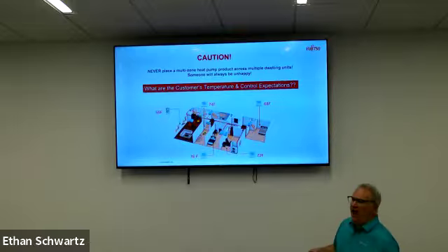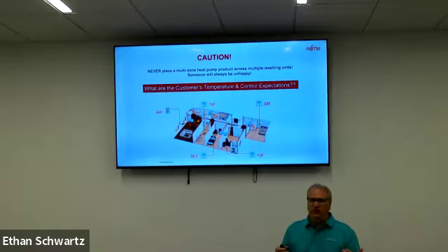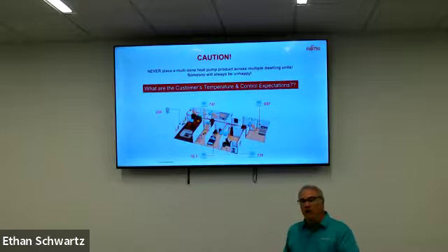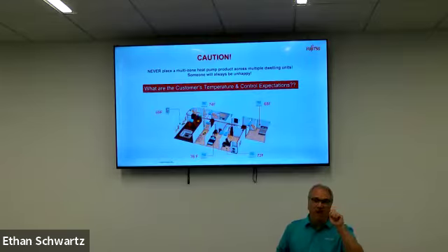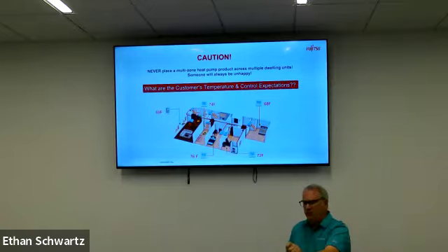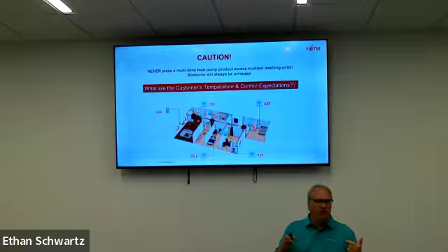If you're going to a mini split or an H series, there's no offering that Fujitsu currently has to be able to put those all in one central controller. We could do that through the VRF side on our controls, which I'll talk about in just a little bit. But overall, as an H series product, there's no control that would do that. However, on the VRF side, we have centralized controllers that will sit across refrigeration circuits and allow that occupant or manager to go to that controller and say, I want that room at this temperature, this one at another temperature. And if it's hooked up to heat recovery, you can determine if those are going to be in heating or cooling. So that's called a centralized control.